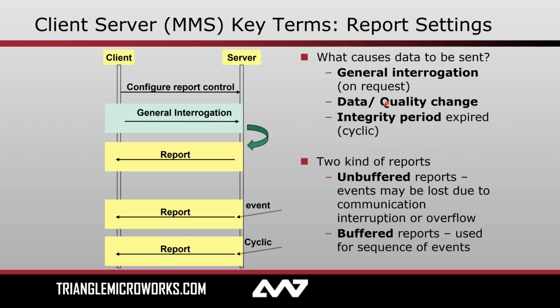So next, I just want to make you aware that there are two types of report control blocks: buffered and unbuffered. The difference is really somewhat self-explanatory by the name. An unbuffered report control block has no buffer, a buffer being a place that we can store events before they are sent out from the server to the client. Whereas a buffered report control block contains a buffer. So if communication is lost or interrupted, those events that might occur before communications are reestablished have a place to be stored and then can be sent up to the client.